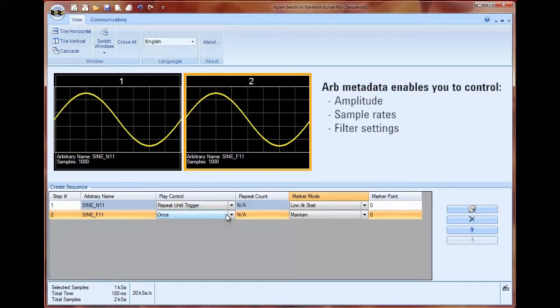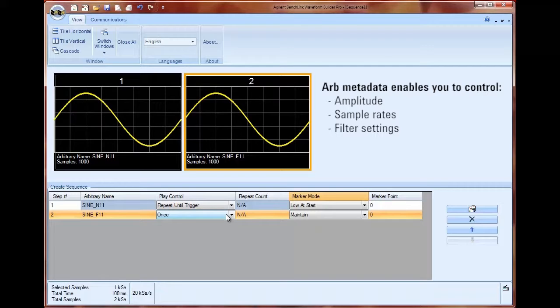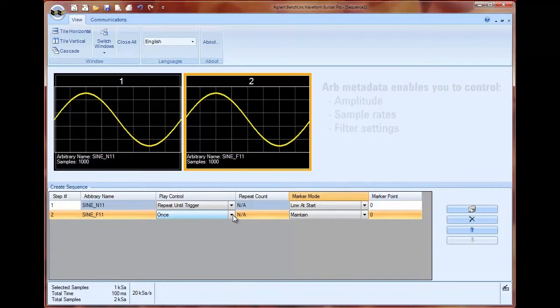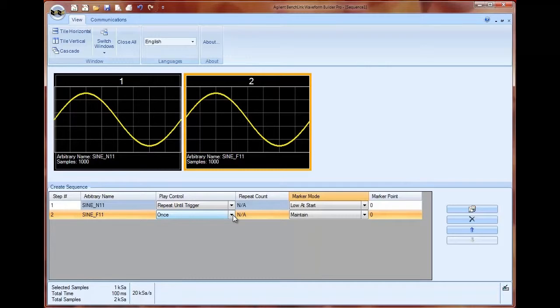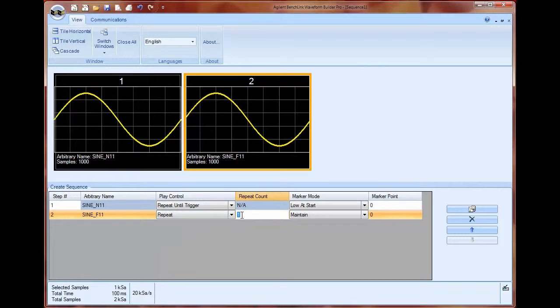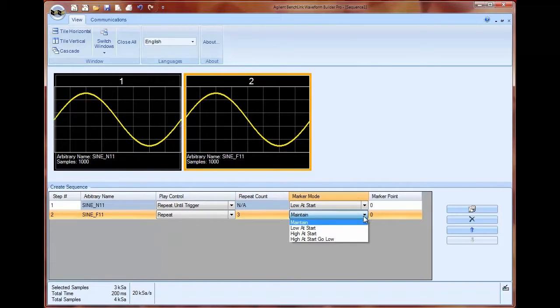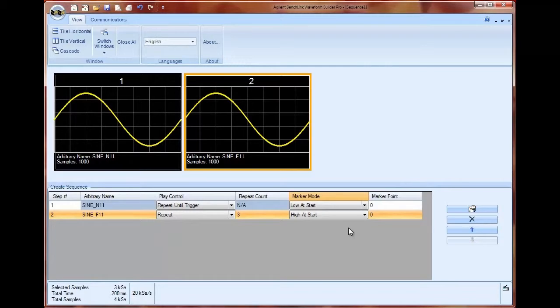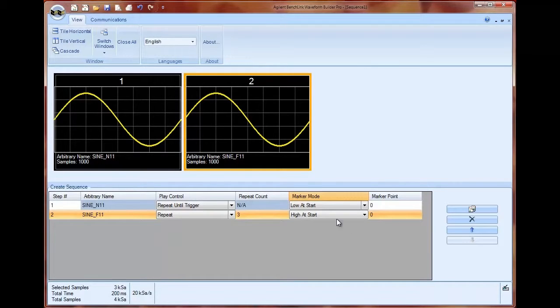Instead of manually changing the voltage settings on a standard sine wave I'm using arb metadata to specify the amplitude. Arb metadata also contains information for sample rate and filter settings in case you want to change those as well. For my play control this time I am going to repeat this one smaller segment three times every time I press the trigger and I'm going to set my marker mode to be high at start. This gives me a trigger that I can use on my oscilloscope when I'm testing multiple pieces of equipment to allow me to see exactly when my faulty signal is coming in.